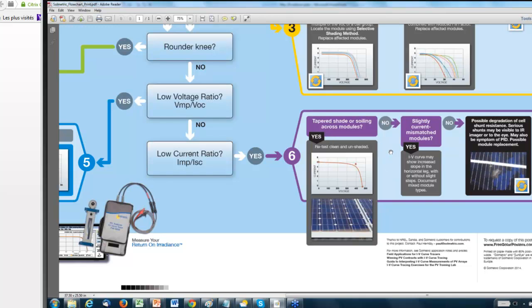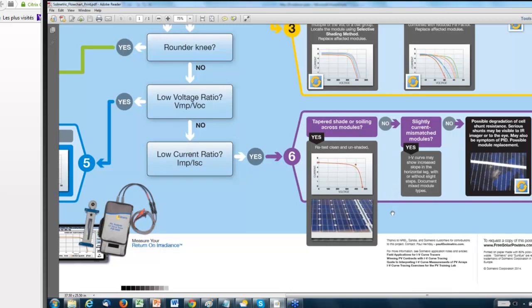And this is an interesting one. This is very interesting, and if you're working in the outdoor training lab, this is a really good one to include. It turns out that if your modules are mounted in the portrait orientation and you have a sloped, a tapered dirt band at the bottom edge of the module, that will cause exactly this behavior. It's not enough difference from one cell group to another to cause a visible step from the turning on of your bypass diodes. It simply mushes it all together and creates this slightly increased slope.